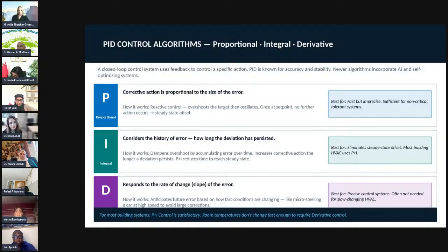For proportional control, this is the corrective action for the size of the error—fast but imprecise, sufficient for non-critical tolerant systems. Integral control is best for eliminating steady state offset. Most building HVAC uses P and I, proportional and integral. Lastly, derivative control gives precise control, often not needed for slow changing HVAC.